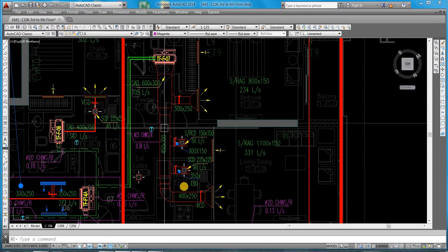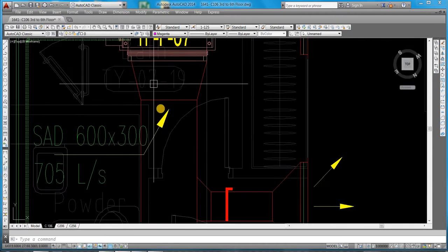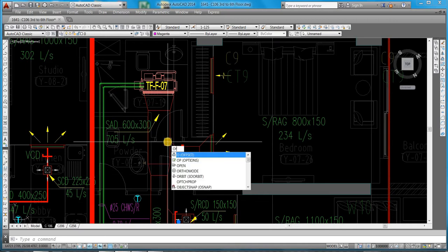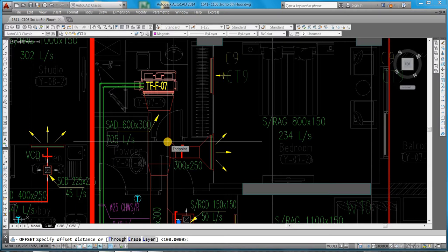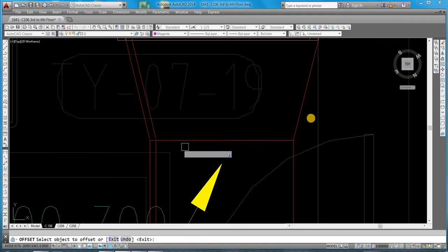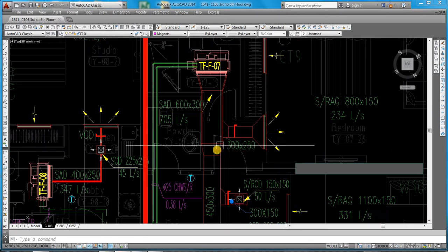In this case, I forgot to tell you about insulation. There is insulation also. From the FCU to the duct area, we need to make inside insulation. This is acoustic insulation, 25 mm thickness. For all FCUs, from the start to the FCU area, 2 meters is required.